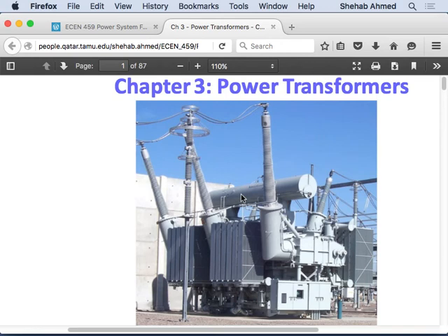Expands. Okay. And then how about if you have this fluid in a closed area and you have cold and hot fluid? What happens to the cold fluid? Cold fluid will be at the bottom and the hot fluid will rise, right? So that's how we cool a transformer. So we have the oil inside the transformer. When it gets hot, it rises, right? Naturally, it can do that naturally, or it can do that by force, by a pump, right?